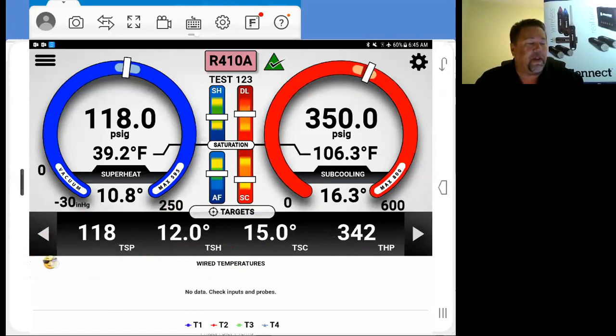There's our targets: 118 on the suction side. As you can see, when we put in that profile, this little tic tac up here, that's our target. On our high side over here, that little tic tac is our target there. We've got a 12-degree superheat target and a 15-degree subcooling target. Now, mind you, I changed that because of the design of the system. You can see that on the nameplate of the condenser. That's where you're going to get it. If you can't find it there, Google is a great resource to get the specs on it. You'll be able to get your design subcooling.